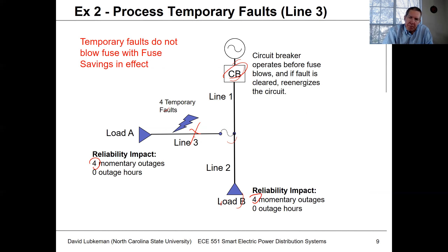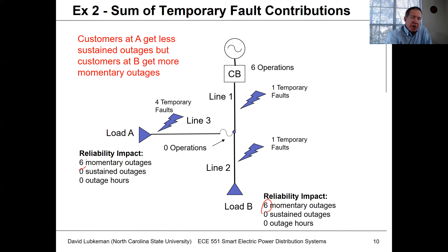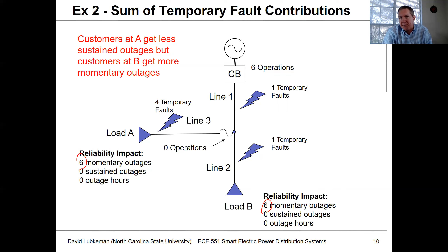Processing the totals for temporary faults shows that we're not getting any sustained outages, but we get a lot of momentary outages. These contribute to our MAIFIE number but not to our SAIFI or SAIDI numbers. The trade-off is that even though load A doesn't see as many sustained outages, load B is going to see more momentaries.